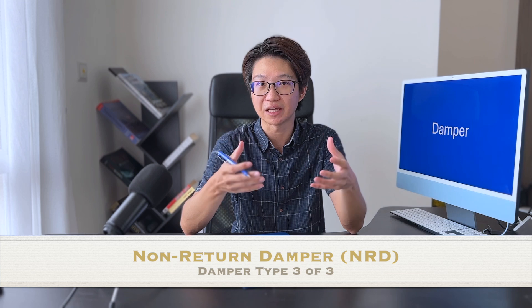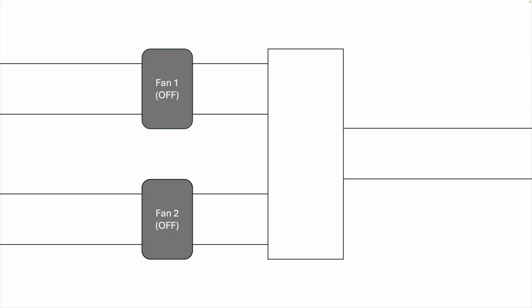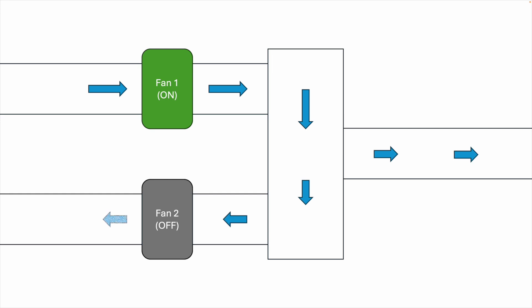The third type of damper is known as the non-return damper, or some people call it the backdraft damper — NRD. As the name suggests, non-return means we want the airflow to flow in one direction and prevent it from flowing backwards. A very typical example is when you have two fans and both fans are connected to one duct. These two fans serve as duty standby or a sequential shift. When you run fan number one, fan number two won't run. After 12 hours you switch over to the other fan. In this kind of system, both fans need an NRD — because when you run one fan, it will blow through both sides: to the main duct and also in reverse direction back through fan number two.